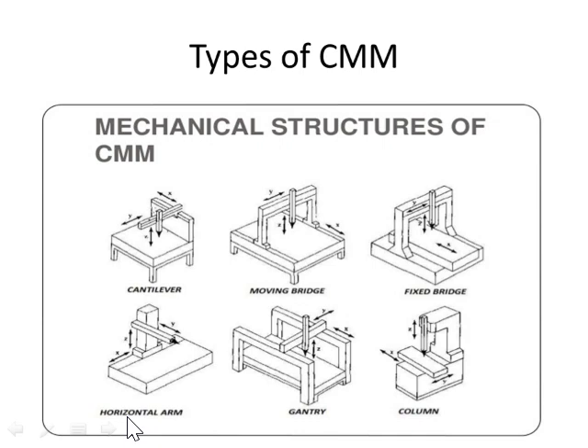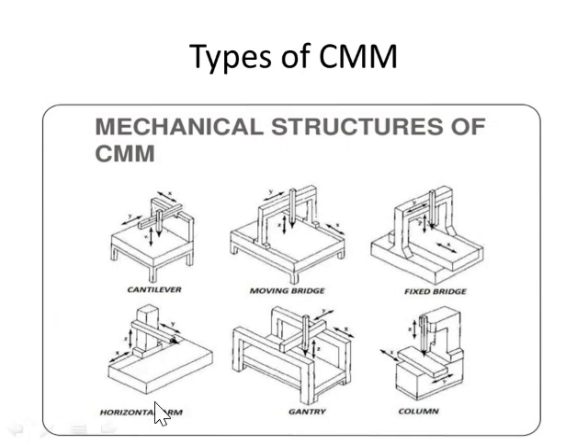The fourth type is called the horizontal arm type. You have a horizontal arm here. This type of CMM is used to find the surface profile of cars. If you want to measure the surface of a car, it is quite difficult with the previous three CMM types, but with the horizontal arm we can easily measure the surface profile.